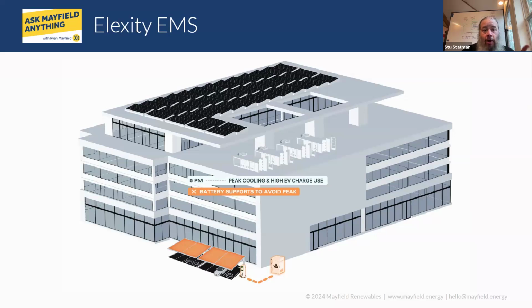Notice we haven't used the battery earlier in the day, except for snapping off the tops of peaks, like fast moving peaks. So we can really reduce that evening peak heavily with the battery, where a more conventional battery-driven DCR algorithm would have been smearing that battery across the whole day. We're able to snap it off and reduce the period where we do that.